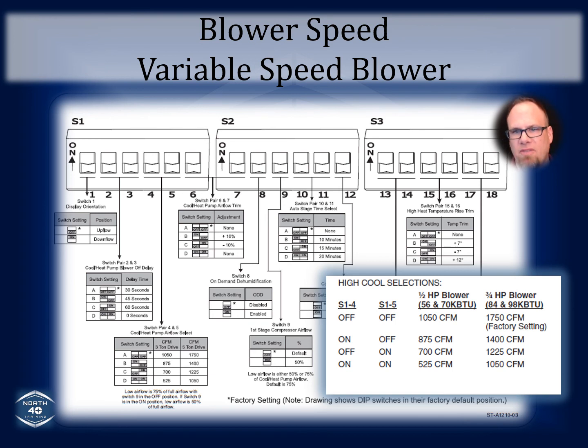Now, once you get up above that 1 inch of static, it goes all over the place. You can't say that it goes down, it goes up. It's kind of a mixed bag. But one thing's for sure, the farther away that you can keep it from 1 inch of static, the better off you are. Now think about it. Okay, you've got a motor with a computer module at the end of it. And that motor with a computer module at the end of it is consistently trying to fight the resistance in that ductwork. And the way that it does that is it's changing its configurations internally to increase the amount of torque that it can exert against that resistance.